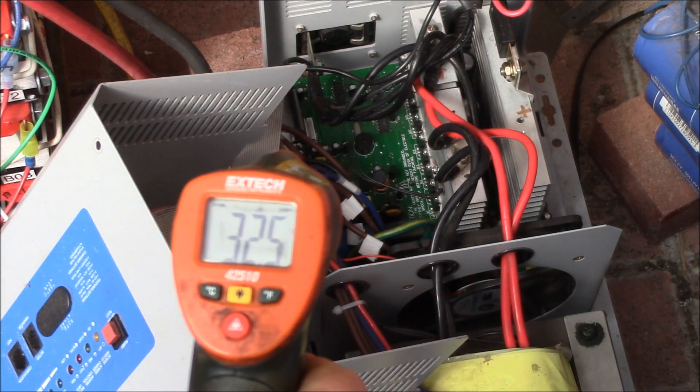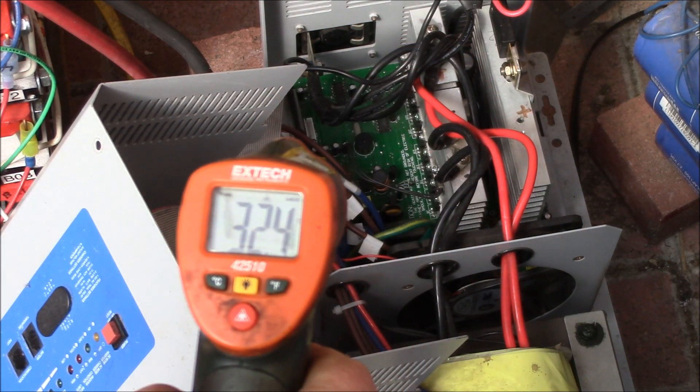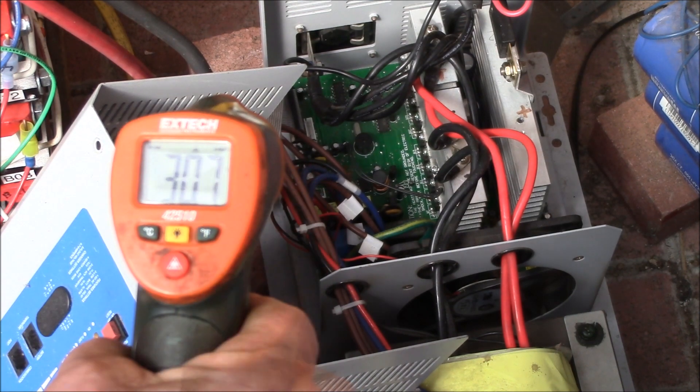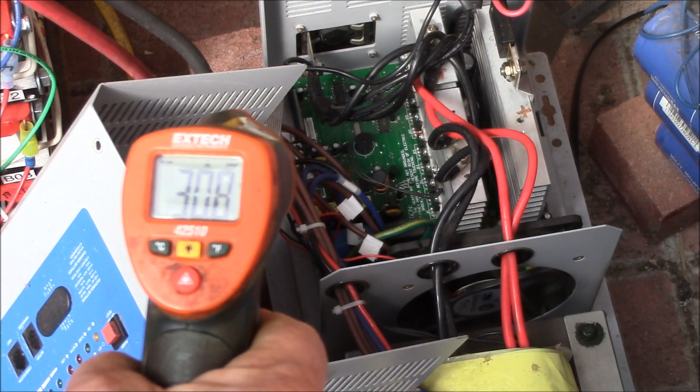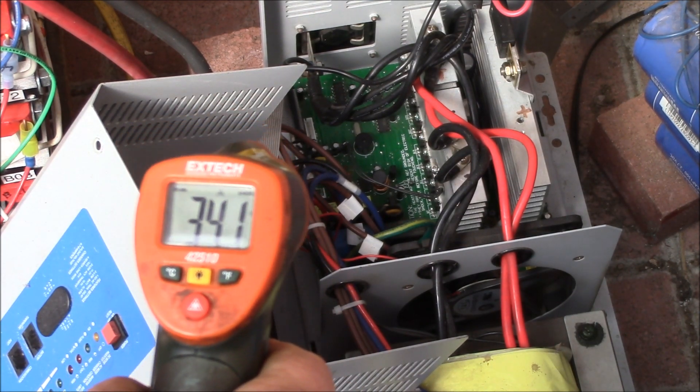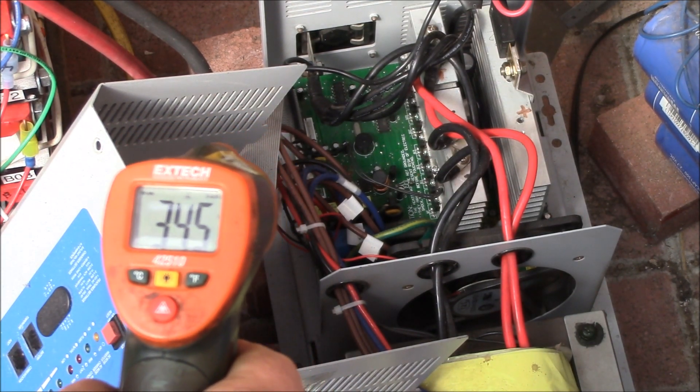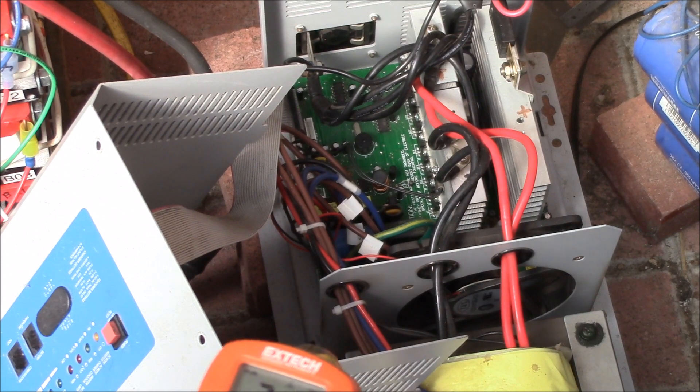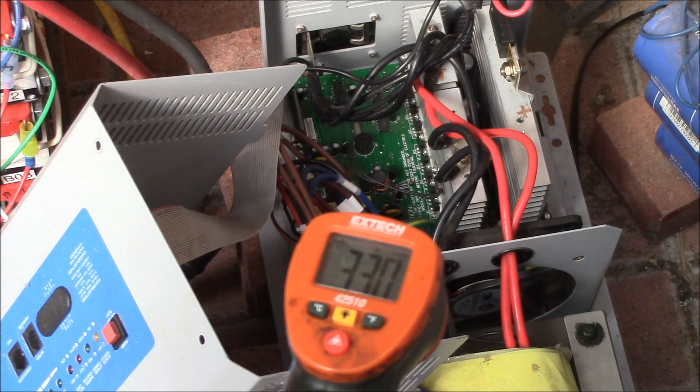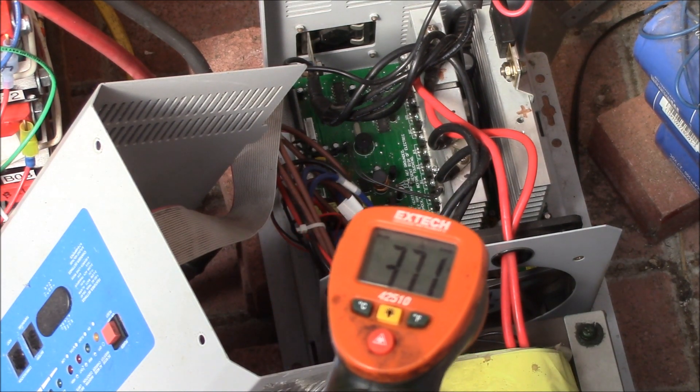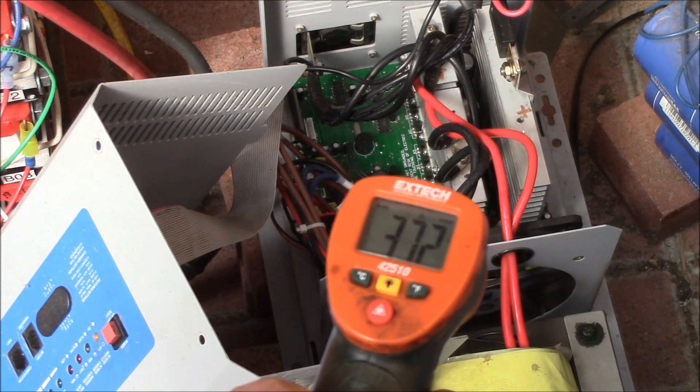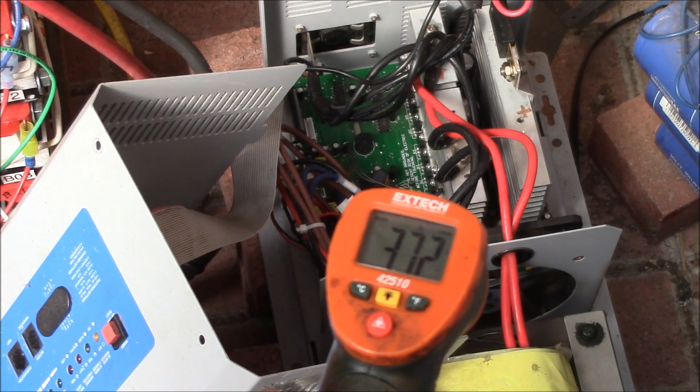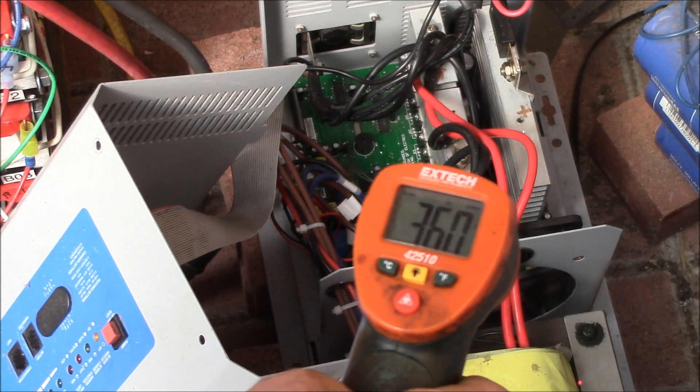If we're down here, we've got about 30, around 30 C on the heat sinks down there. And if I'm on the transformer here, actually the transformer is about the hottest thing. I've got about 37 C.